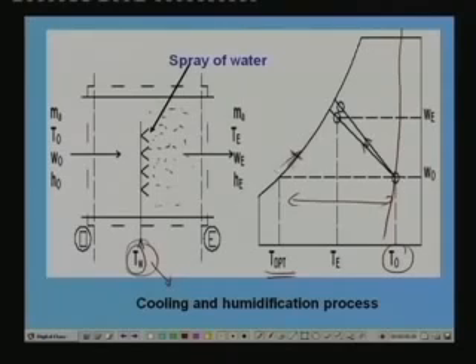Then what happens? Since its temperature is lower, the air temperature drops, and since the vapor pressure of the water is higher than the vapor pressure of air, some moisture evaporates from the water droplets and moisture is added to the air. That means air gets humidified, and from the straight line law we know that if you know this point and the inlet condition, the exit condition must lie somewhere here on this line. So you can see that the process will be somewhere along this line or along this line depending upon your temperature. So what is happening? The temperature is reducing, at the same time moisture content is increasing. The moisture content is going up, right. So, this is the cooling and humidification process.